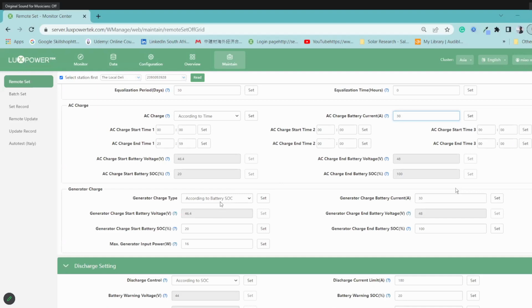So you have your generator, so it's pretty much the same, set it to SoC voltage, and then just make sure that you put the correct information in over here. All right, so 16 is the default. And then also the generator charge battery current. Take that into account too if you have more than one battery.